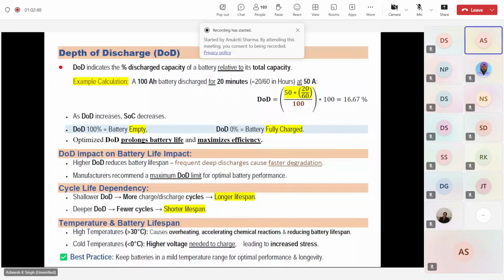Then comes another term, cycle life. Cycle life dependency is also there. If you are using a shallow or lower depth of discharge, more charge-discharge cycles are going to take place - 20% charge, then 20% discharge, again charge. So with this shallow DOD, that is going to result in longer life. But with deeper DOD, there are going to be fewer cycles and a shorter lifespan. I hope I am clear.